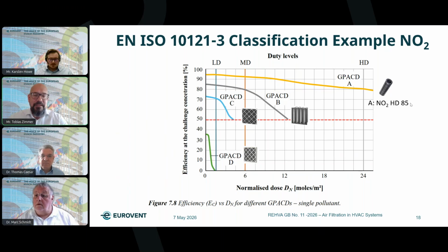That's basically a level of result you will mainly reach using cylinders or other masses of carbon. So when we look at the second filter, this compact filter, so it's a 2-in-1 compact filter, particle filtration and gas filtration, you would start in the same approach. As you can see, it starts lower at 85. We load until a light duty dose, still high efficiency. Continue to medium duty. You already reached 80%.